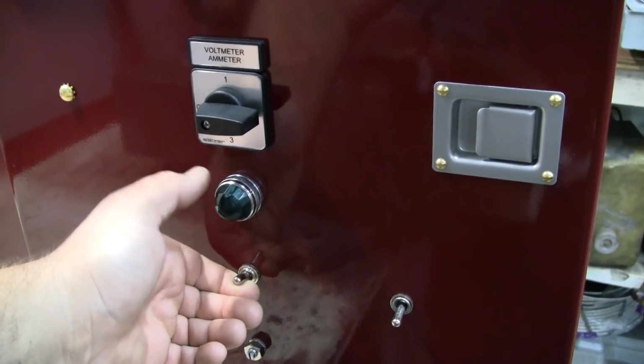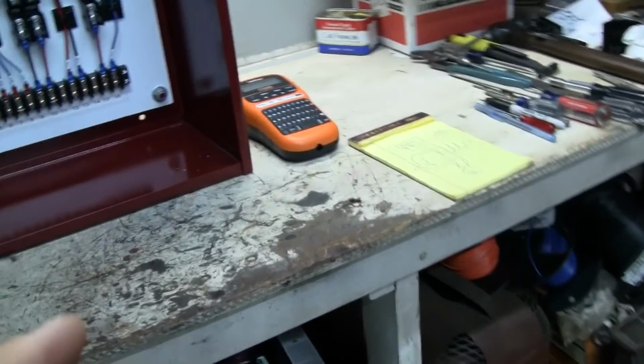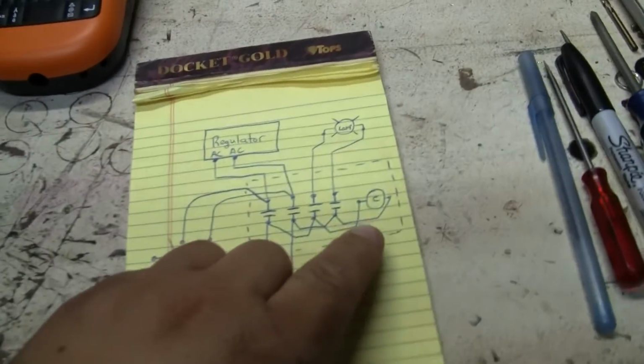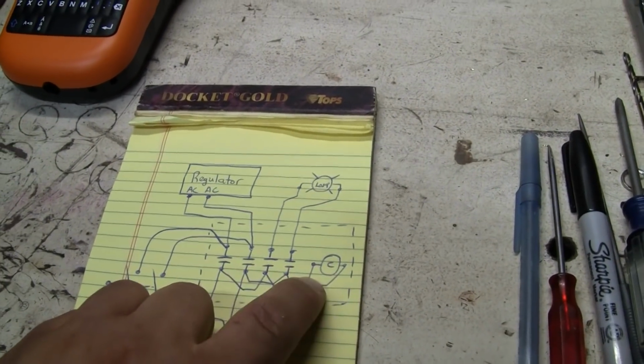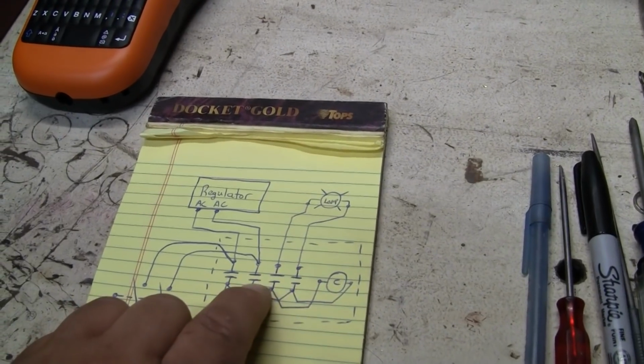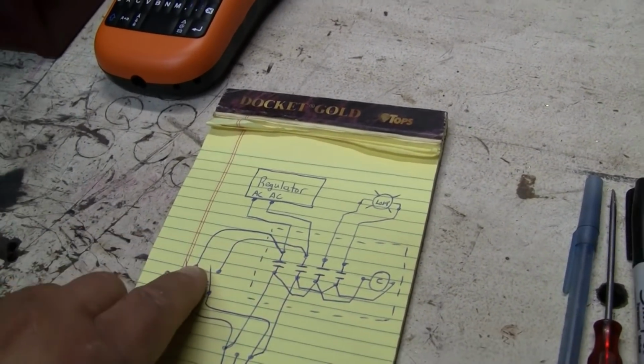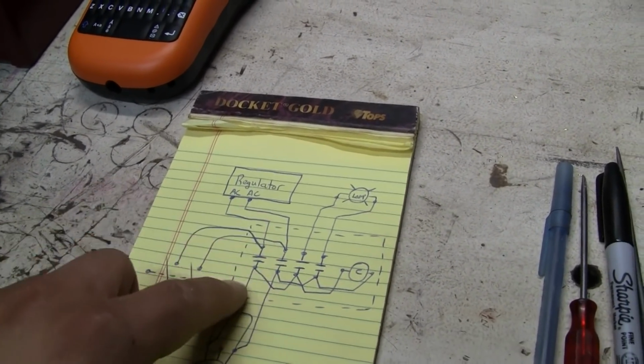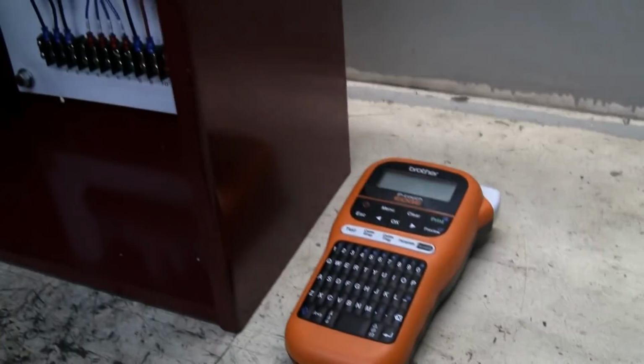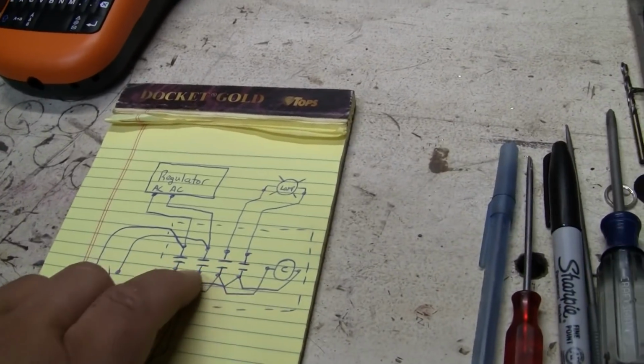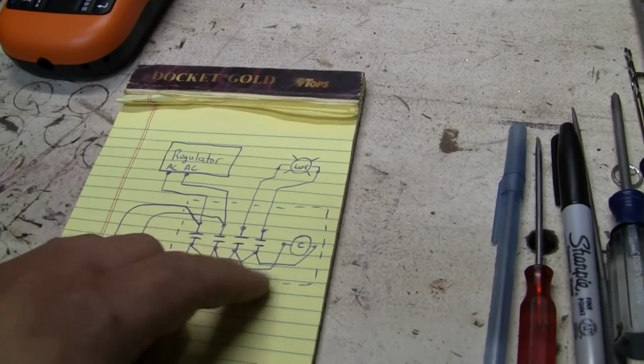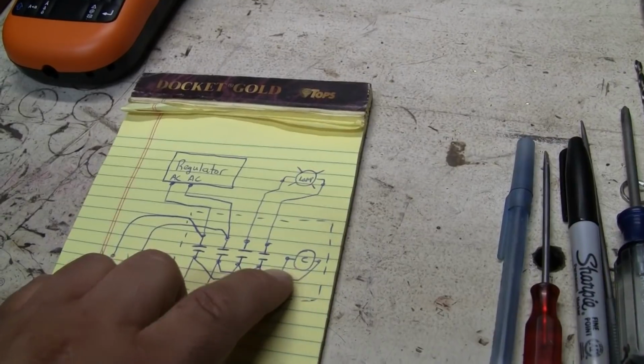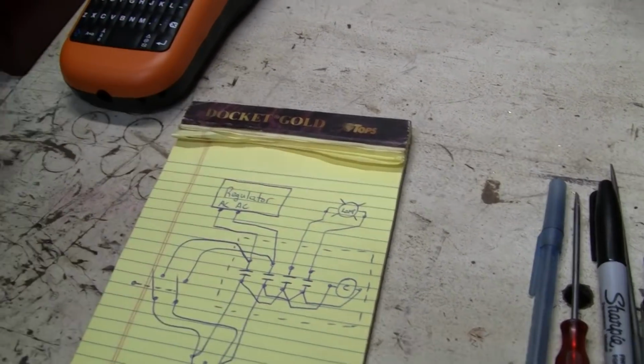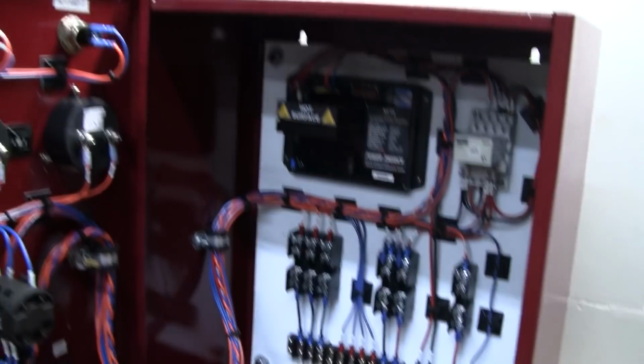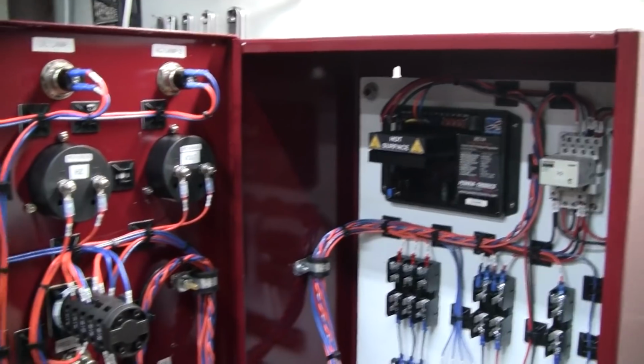Once this lamp lights up, that means that the generator has built up enough output voltage to close these relay contacts, to energize that coil and close these contacts, and you can drop the switch out, and then the regulator will be directly powered off the generator through this relay. Also a little bit of protection: if the regulator or the gen's output ever drops below the dropout point of this coil, this relay, this set of contacts will drop out and the regulator will be shut off. So ideally that will never happen, but you never know.